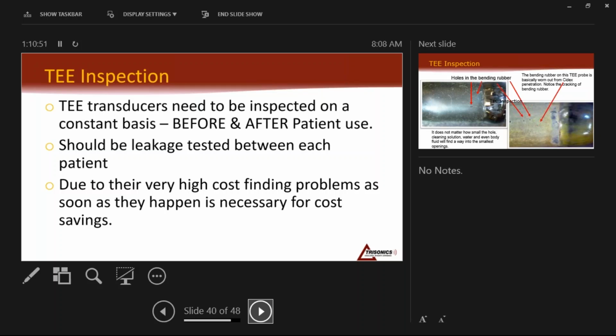They need to be leakage tested between each patient. And this is one probe that when you find anything wrong, you want that to go out the door that day. Because if water has gotten inside there, we need to get it into a probe lab and get it open and get that water drying out immediately. It only takes about 72 hours for water to actually develop corrosion. That's if it hasn't even hit the array. If it hit the array, the probe's done in all modern probes, but it really needs to happen pretty fast.